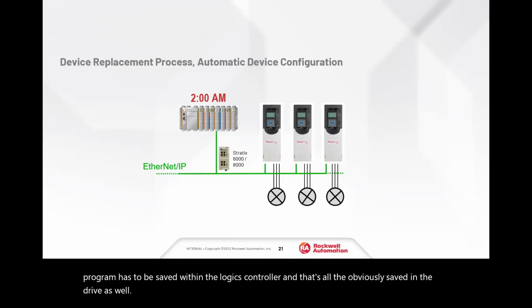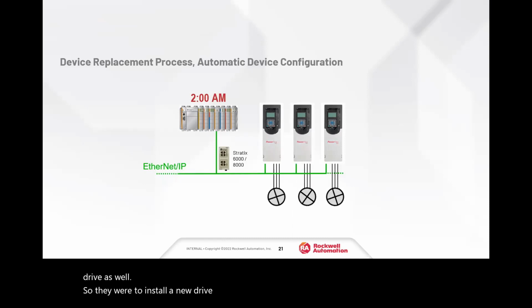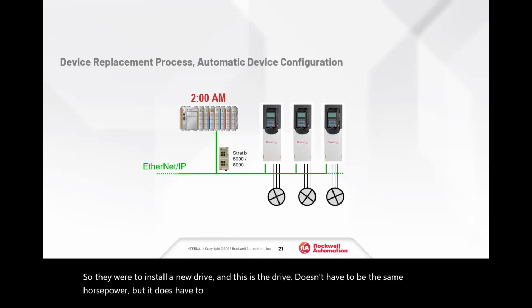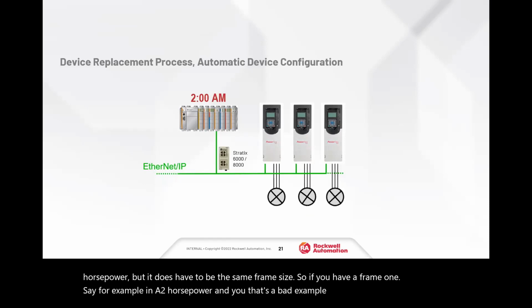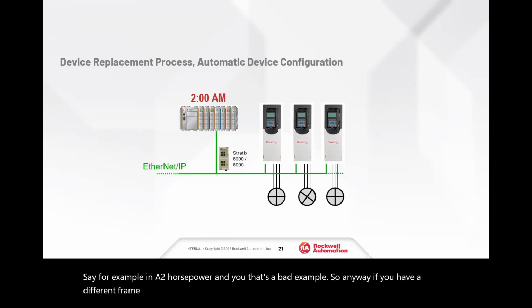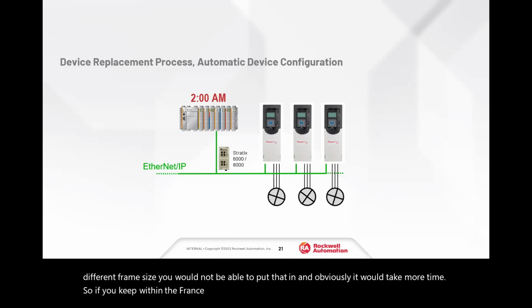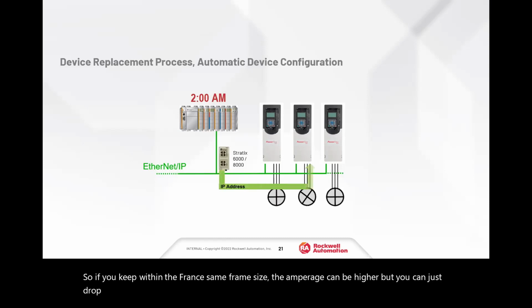So if they were to install a new drive, the drive doesn't have to be the same horsepower, but it does have to be the same frame size. If you have a different frame size, you would not be able to put that in, and obviously it'd take more time. If you keep within the same frame size, the amperage can be higher, but you can just drop it into the slot there.